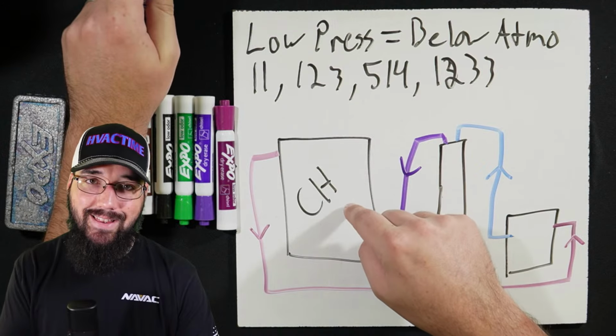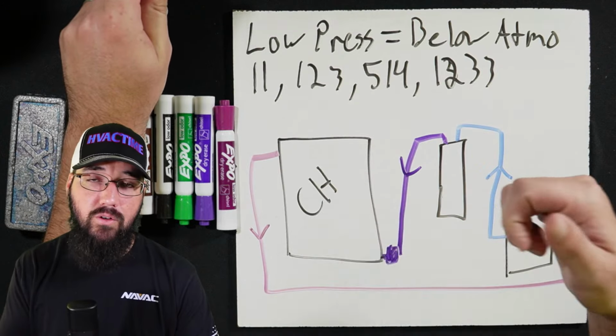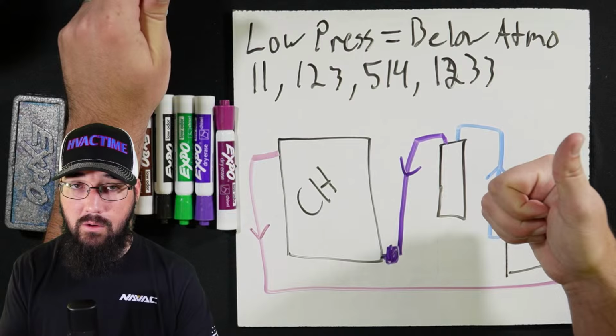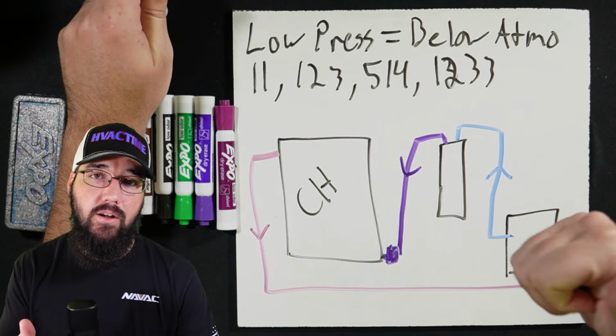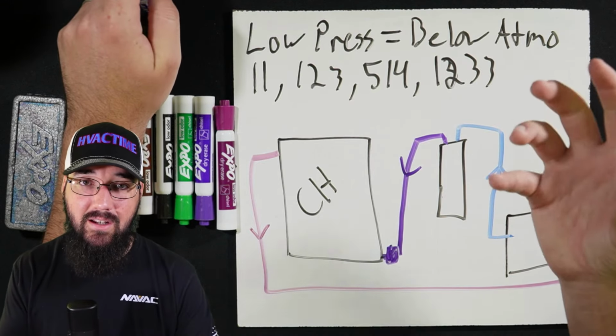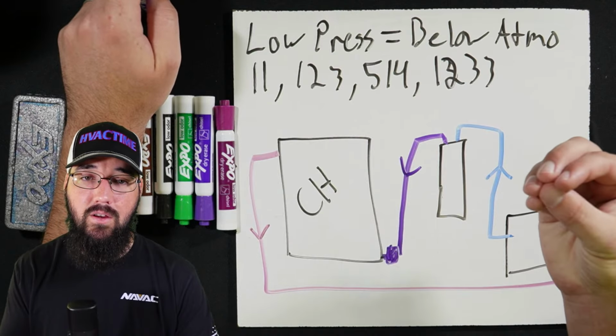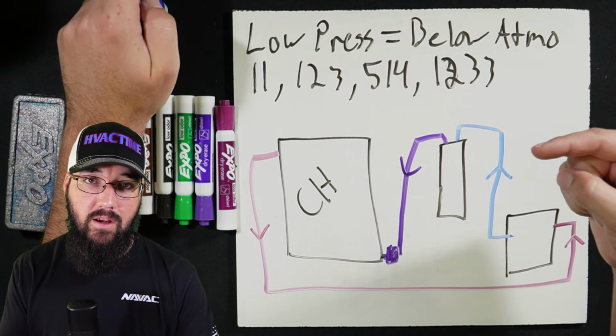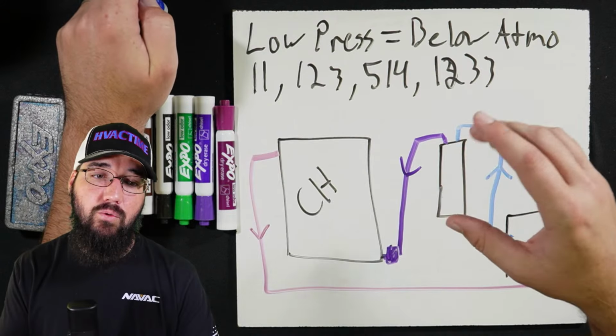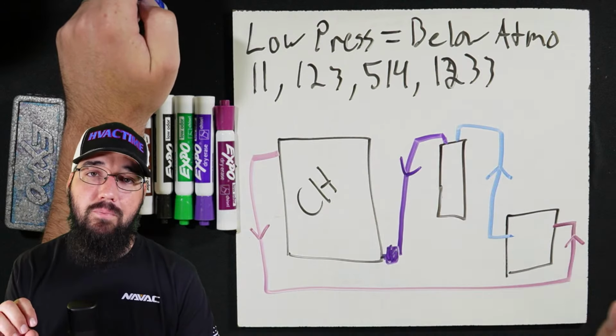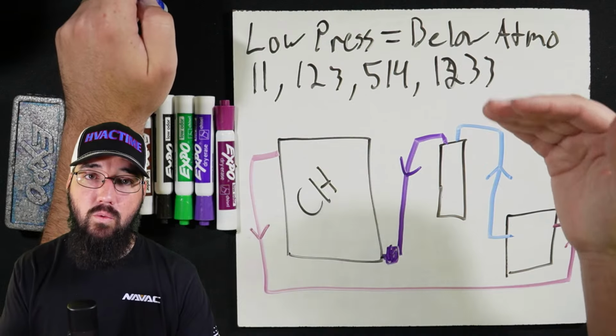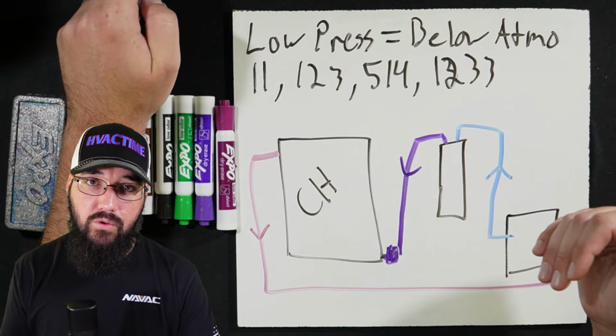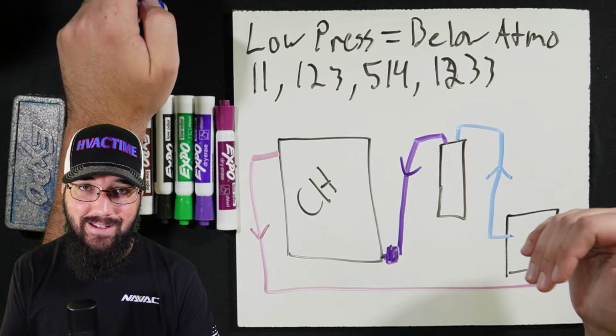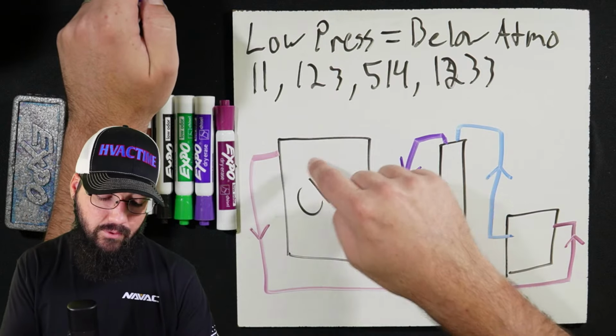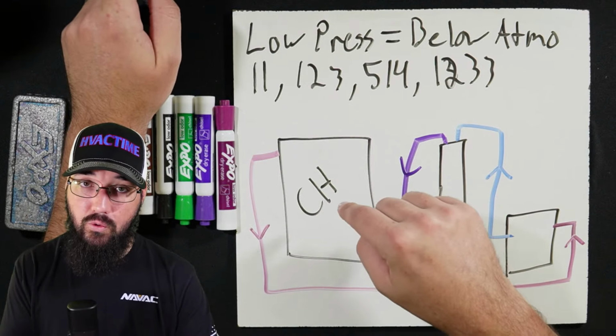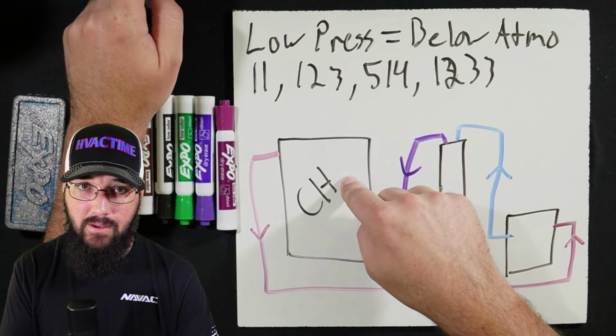On a machine like this, when we're talking about these centrifugals, we're talking 24 to 72 hour pressure tests. We're talking a 24 to 72 hour standing evacuation or vacuum test. Or after you complete the evacuation and you get it down to below that 500 microns, then you stop. You'll walk away and make sure it holds for the next 24 hours at least. That's what we're discussing.